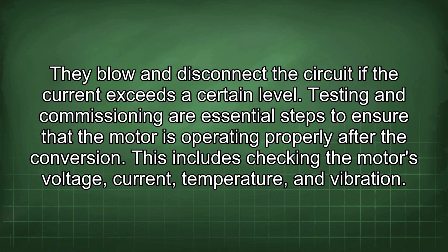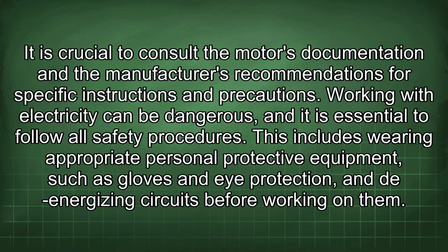Testing and commissioning are essential steps to ensure that the motor is operating properly after the conversion. This includes checking the motor's voltage, current, temperature, and vibration. It is crucial to consult the motor's documentation and the manufacturer's recommendations for specific instructions and precautions.